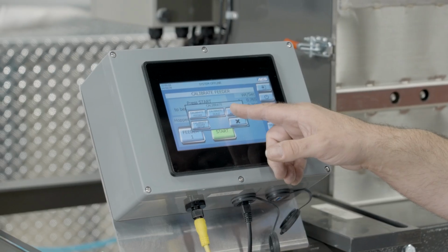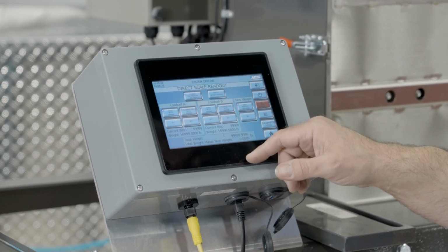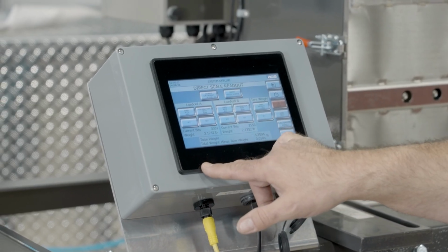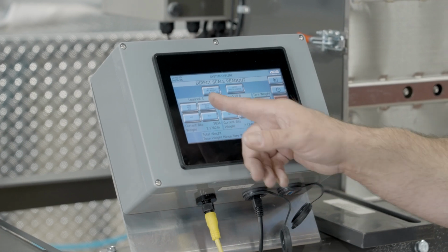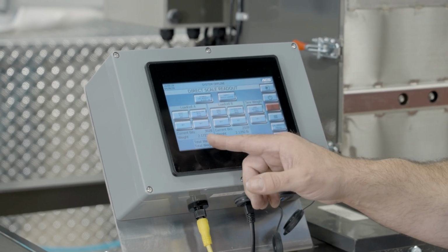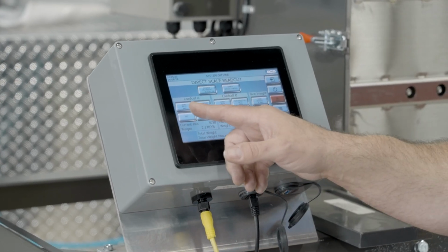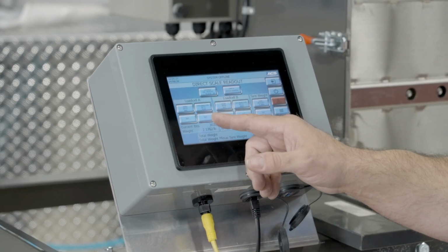The next thing we see here, we already did the calibration before, so we'll look at direct scale readout. Direct scale readout is helpful if you're troubleshooting a load cell issue. You can see we have separate readings for load cell A and B. We show the current weight, current bits, and then up here we show the last calibration 0 bits and last calibration bits.